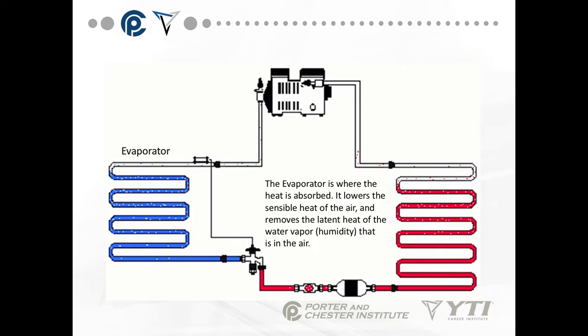Then you have the evaporator. The evaporator is where the heat is absorbed. It lowers the sensible heat of the air surrounding it and removes the latent heat of the water vapor — which is humidity — that is in the air. The principle behind the evaporator is that this low-pressure refrigerant coming in has a boiling point lower than the air surrounding it.